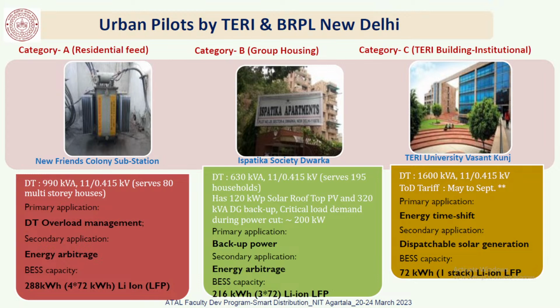They are demonstrating the use of storage for 3 different applications. One is to reduce overloading of a transformer—they don't want to replace it since it was getting frequently overloaded. So after 80% loading, they will switch on storage support so it never gets overloaded, increasing its life. That is the overall objective.